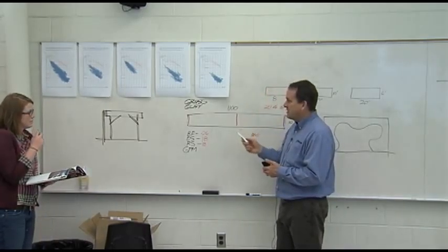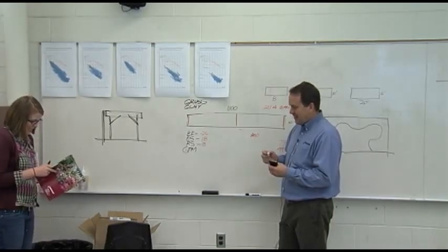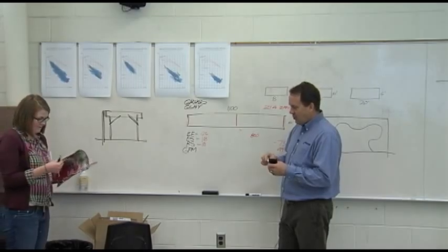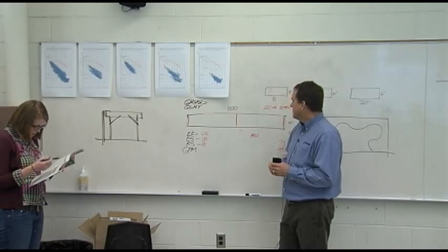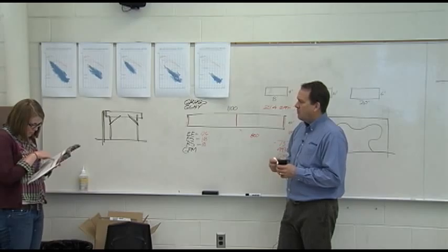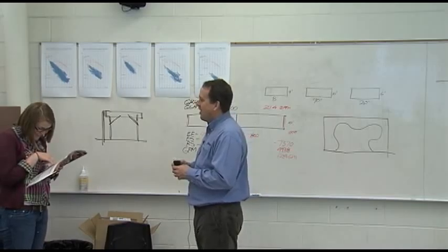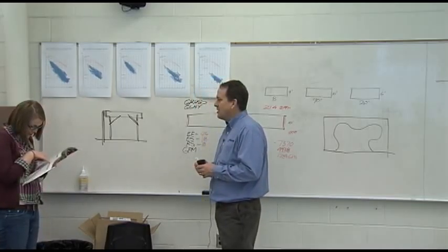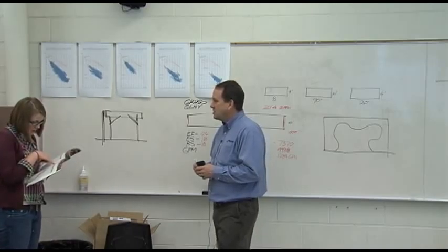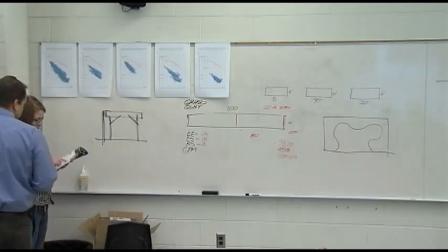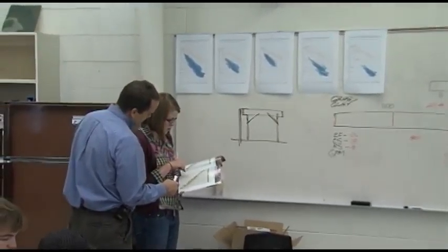So what size of pipe does this need to be? And let's say that we can't exceed 7.5 feet per second on schedule 40. I'm going to need this. Team, anyone know? So it's the shaded area, and just before it transitions into the next shade is typically where you want to be at.